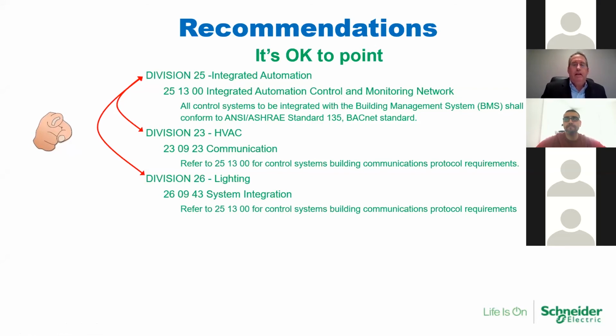Same thing in the lighting. Say you want to use BACnet for your lighting control systems. You put that in Division 26, and you point back to Division 25 for the actual specification that you're going to use BACnet.